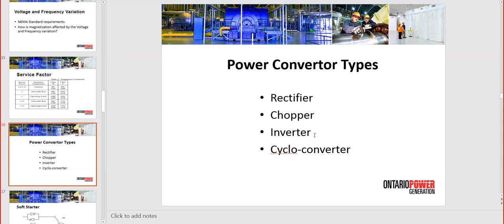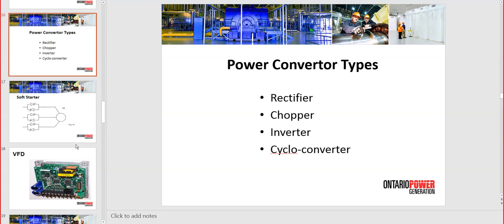Now the new ones are also built with capacitors, so there are capacitor types, but you can still have the older type. For instance, Rockwell provides that, manufacturing in its Waterloo division. That's the power division of Rockwell, and they have the PowerFlex 7000 series, which is called a current inverter, not a VFD. It is actually a rectifier and an inverter with a large coil on the DC with an air gap to avoid saturation. The problem with this type of VFD with a coil is that the coil needs to be about 10 times the motor inductance, so you need to change the coil if you change the motor type. So that's the big disadvantage of these current inverters.